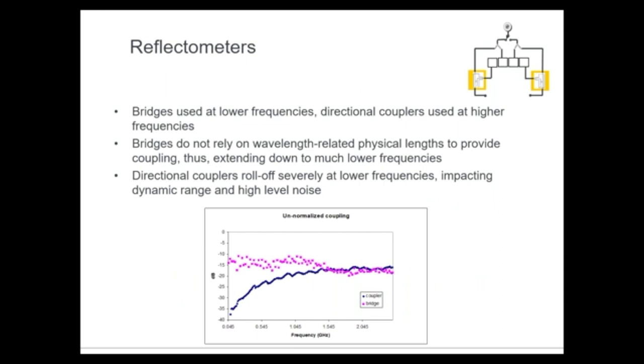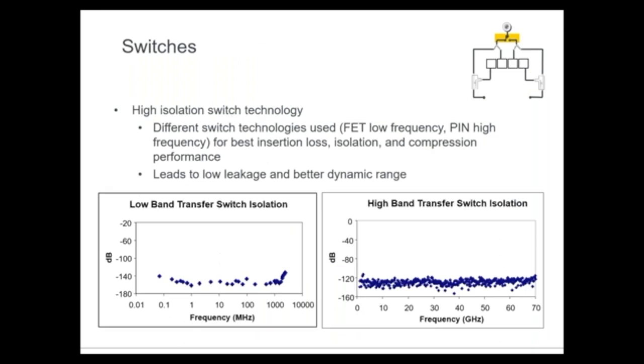For reflectometers there are two distinct approaches. Directional couplers are typically used at high frequencies in microwave VNAs but are wavelength-dependent, so they roll off at lower frequencies. Directional bridges are used more in RF VNAs and work well at low frequencies. Ideally, you'd combine both to create the most broadband VNA possible. Similarly for switches: FETs are used at low frequencies, PIN diode switches at higher frequencies, to optimize insertion loss, isolation, and compression — specifically the IP3 or IMD performance of the switch.